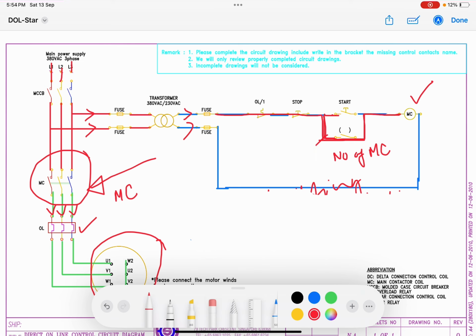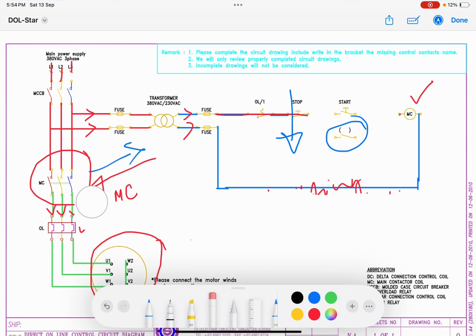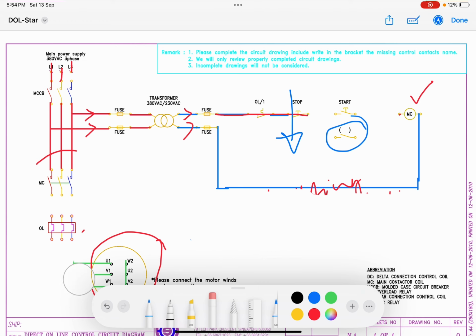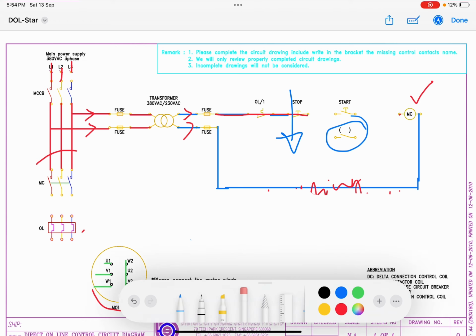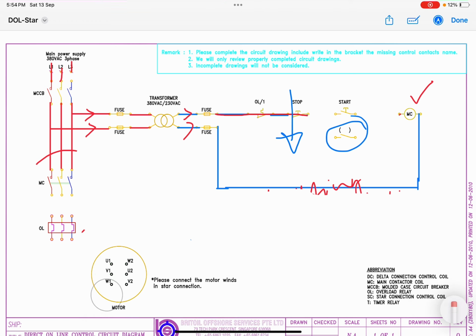For stopping, what do we have to do? For stopping, we can do one thing. Once we press the stop button here, right, the power supply across your magnetic contactor will be cut out, right? So once the power supply across the magnetic contactor is cut out, all these contacts will be in open position. Also this main contact is going to open. So as soon as your main contacts open up, right, now there is no power supply across your motor winding. So the motor will lose power supply and then it is going to stop.